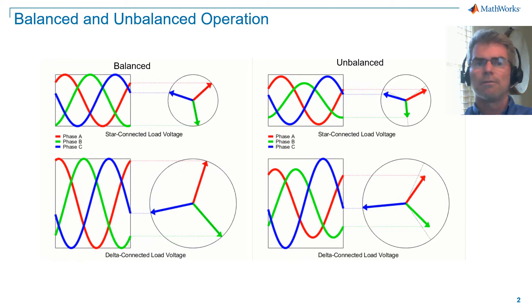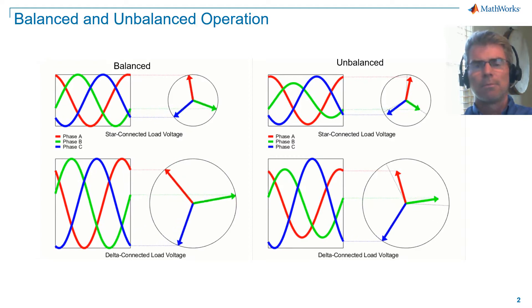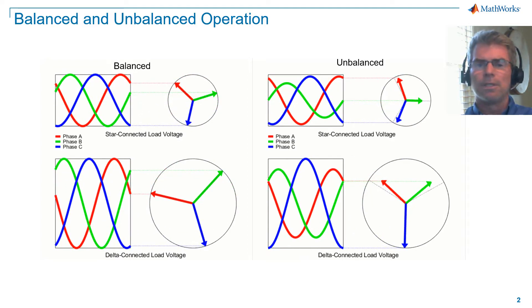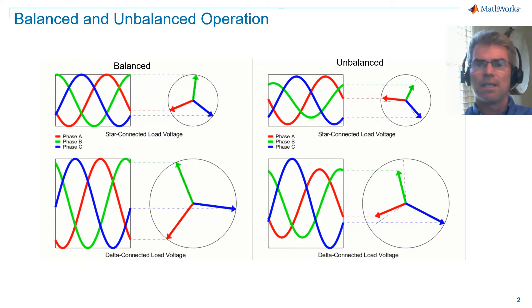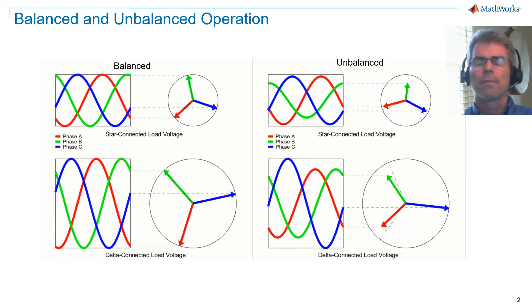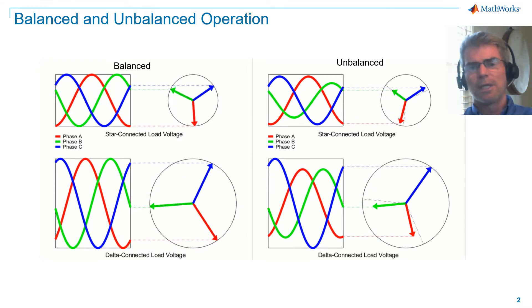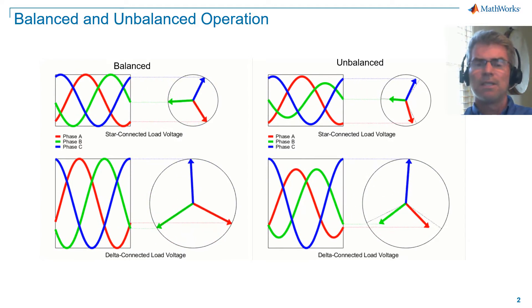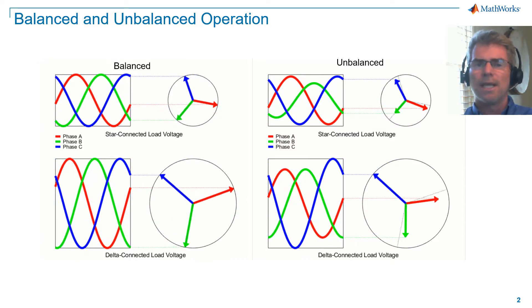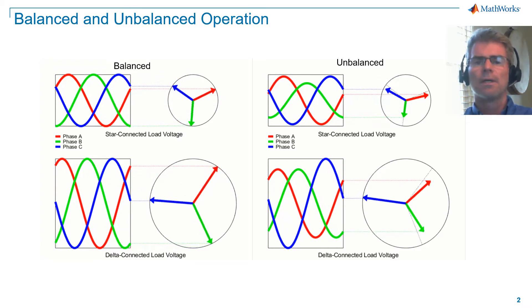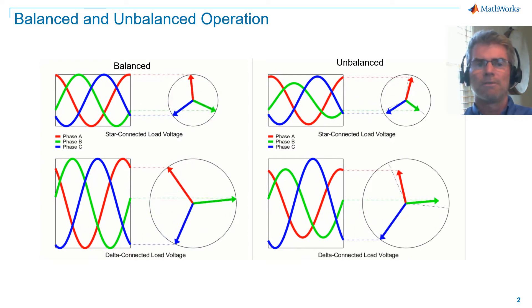Here we can see a visual representation of a balanced system on the left and an unbalanced system on the right. Balanced three-phase voltage has equal voltage magnitudes in each phase, with phase B lagging phase A by 120 degrees and phase C leading phase A by 120 degrees. Similarly, balanced three-phase current has equal current magnitudes in each phase, with phase B lagging phase A by 120 degrees and phase C leading phase A by 120 degrees. An unbalanced system is anything that does not meet this criteria.